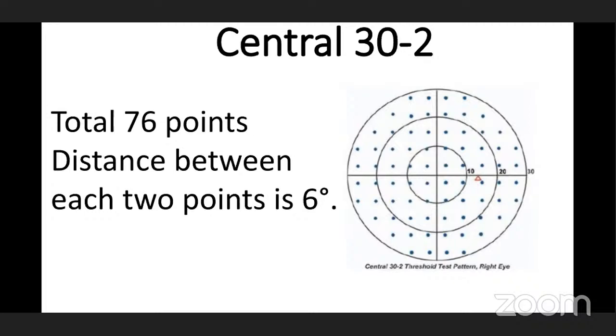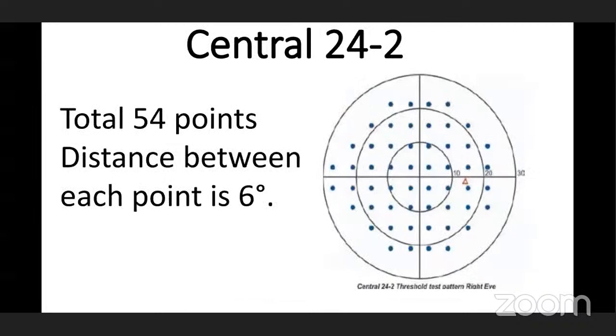Central 24-2 is the default test. We check 24 degrees of visual field area with a total of 54 points and 6 degrees between each point. At the nasal area, there are two extra points, which indicate that this test is useful for detection of early glaucoma.